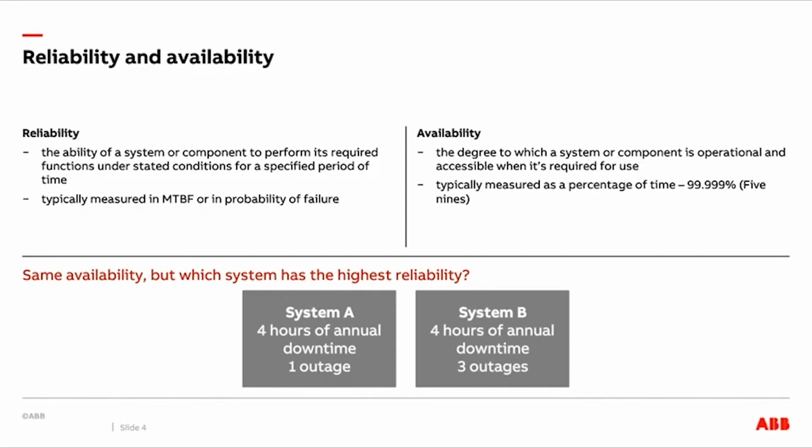It is difficult to get accurate mean time between failure data for most of the electrical distribution equipment, like circuit breakers. The modeling is complex, and it's very expensive to have these kinds of studies done to do the calculations. So we'll probably see a mix of reliability and availability used in assessing various data center designs.